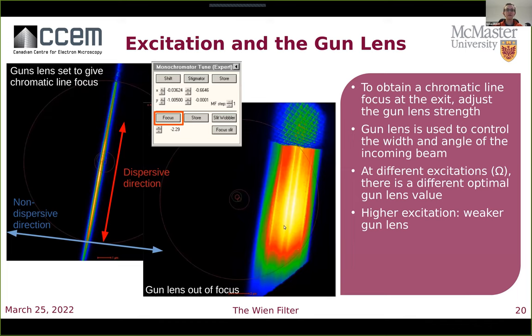At a low excitation, the gun lens needs to provide a strong focusing power to give the entrance of the mono a convergent beam. At an excitation of approximately π/2 or 1.6, the gun lens provides approximately a parallel beam from the emission cone of the tip. At a high excitation, only a weak gun lens is needed to provide a slightly divergent beam. When the gun lens — listed as mono focus in the alignments — is set perfectly, the user should see a very sharp dispersed line. When it's away from the perfect strength, the beam broadens in the non-dispersive direction and shrinks in the dispersive direction as we move toward having an achromatic image of the mono entrance aperture.